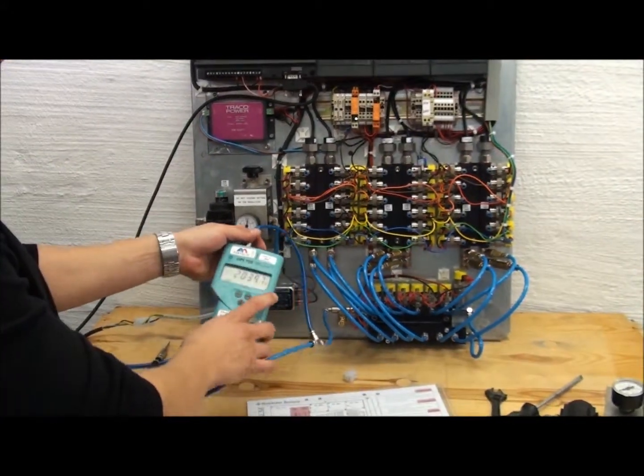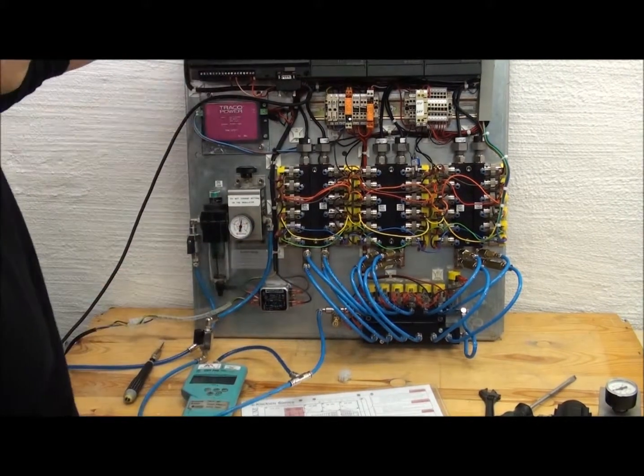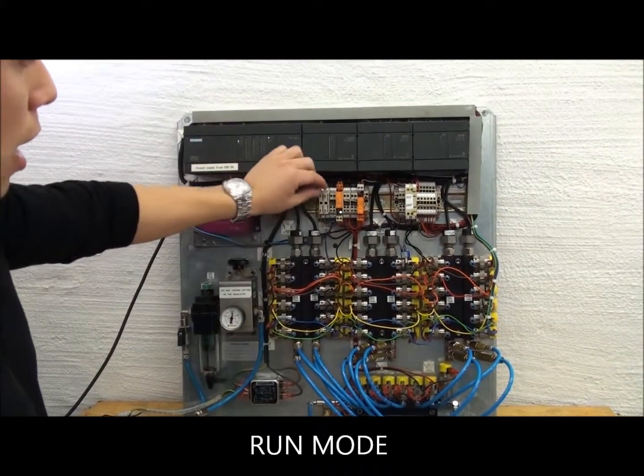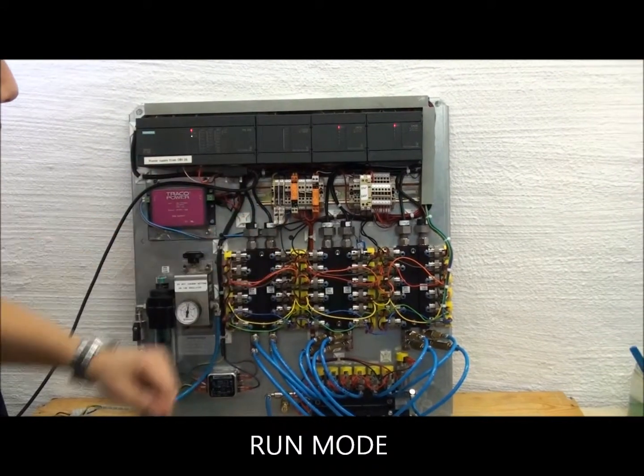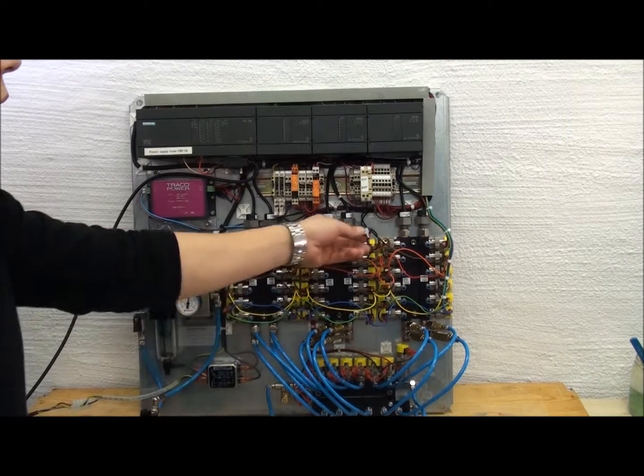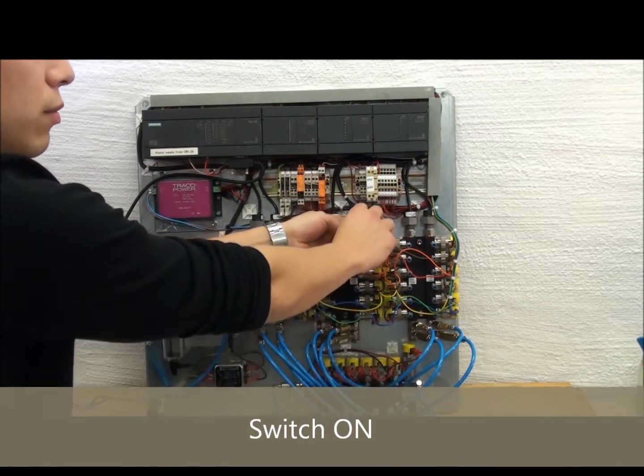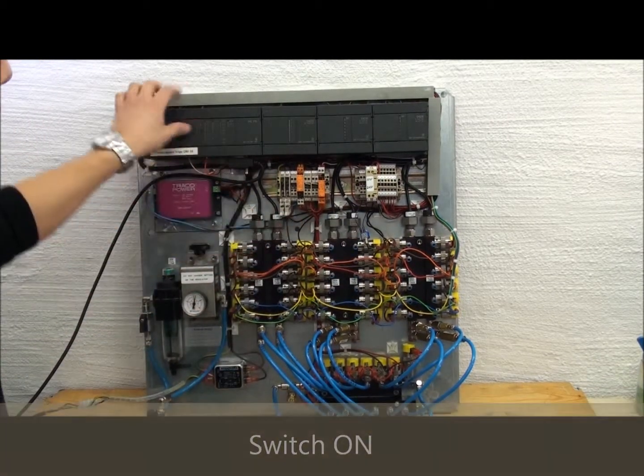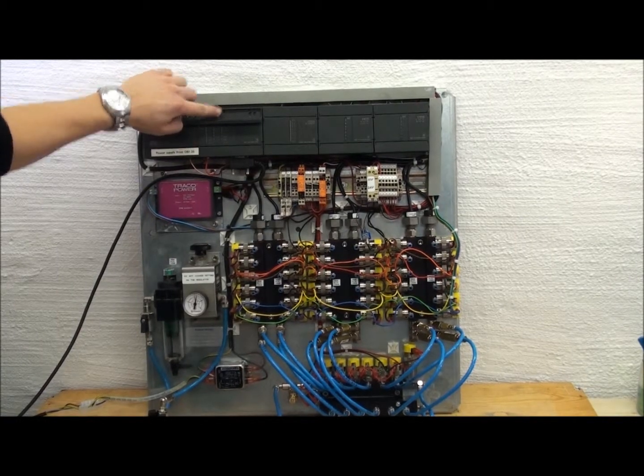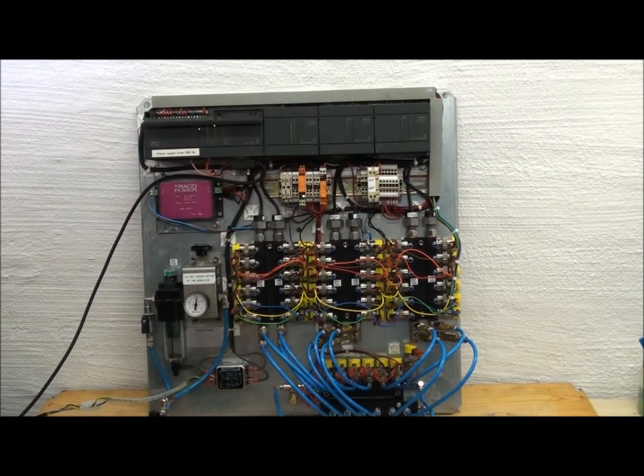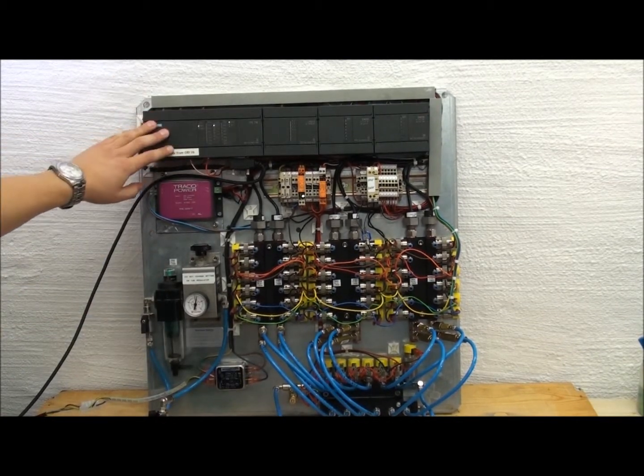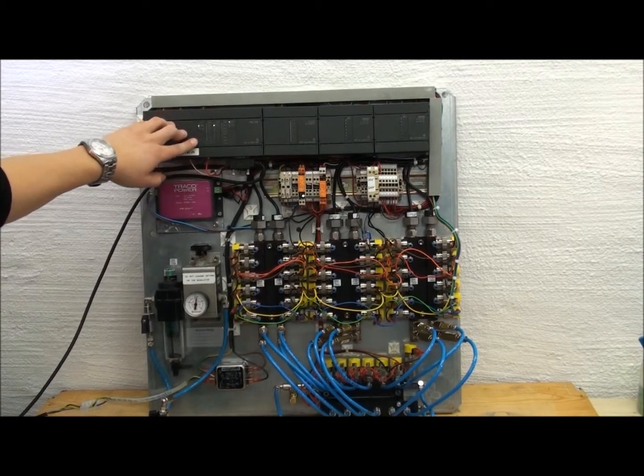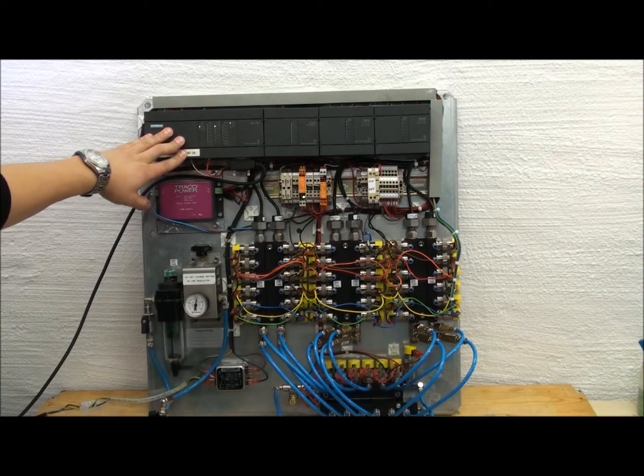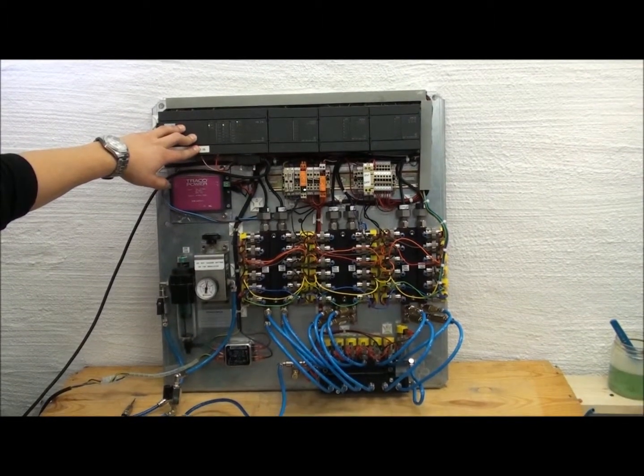After you're completely sure that the pressure is right, then you turn it back to run mode, and you just break the fuses so that the power goes down. Then what you do is turn the switch on, so you make a jumper in between these two cables. We do that now. Then be sure that the switch is in the run mode. Then you put the fuses on again, so the system just starts to run. We give it around 30 seconds or so. Then it's just to wait and hope that the system is going to be calibrated afterwards.